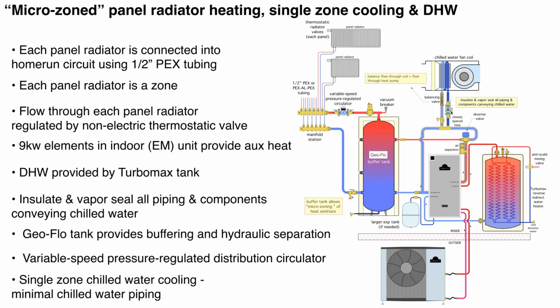And those of you that are new to chill water cooling, it's imperative that you insulate and vapor seal any piping and piping components that are carrying chilled water. We talked about those details in one of the previous webinars. Make sure you get some insulation around the circulator volute, all the piping. The diverter valve that I've got here, see the insulation is around the valve body, but not around the actuator head. Same on a circulator. You don't wrap the motor can of the circulator with insulation. I would recommend you put a balancing valve in here that will allow you to set and measure the flow rate going through the chill water coil to get that balanced out.